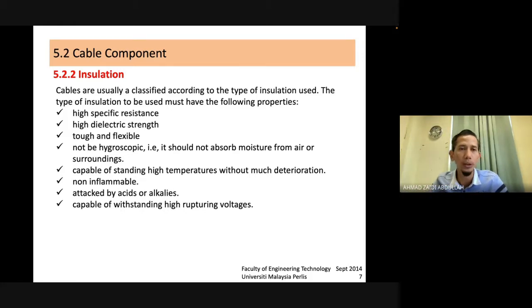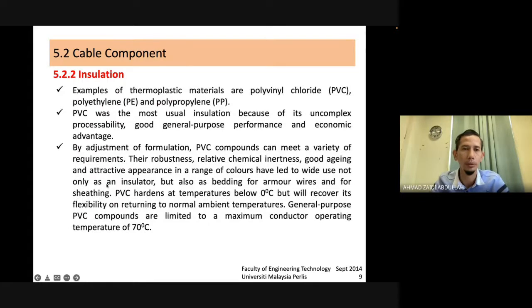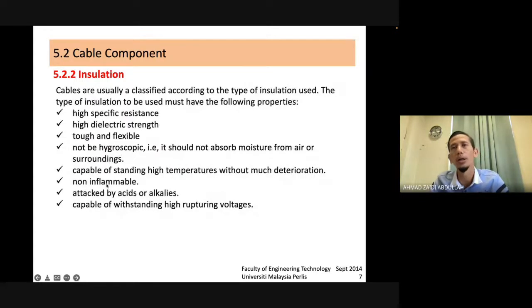Okay, for the non-inflammable, normally it is just for MICC cable, which is a cable for generator set. Okay, kalau if you select non-inflammable cable insulation for normal cable, so confirm lah your project will be burst. Okay, because this will affect the cost.